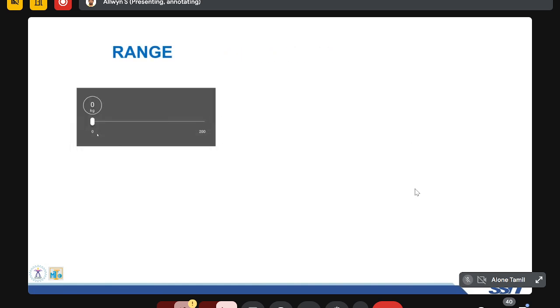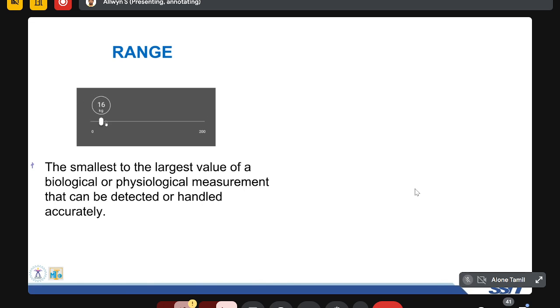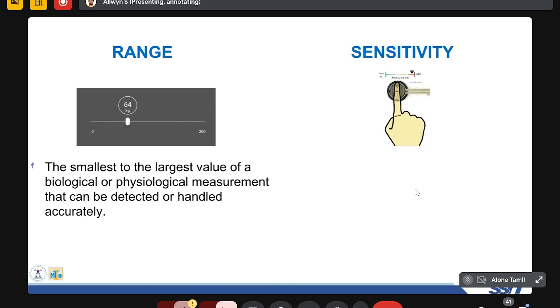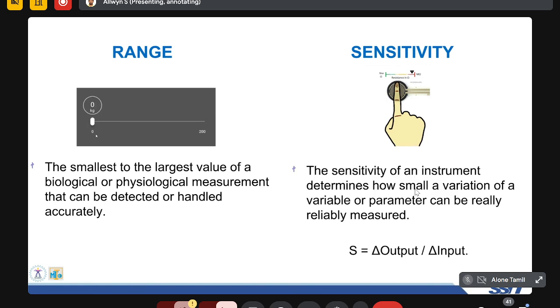Among those, the first measurement is the range. The range is the smallest to largest value of a biological or physiological measurement that can be detected or handled accurately. For example, a weighing machine has a range between 0 and 200. How well can it handle that accurately? That is the range of an instrument. The second one is the sensitivity. The sensitivity of an instrument determines how small a variation of a variable parameter can be reliably measured. It can be calculated by the change in output with respect to the change in input.